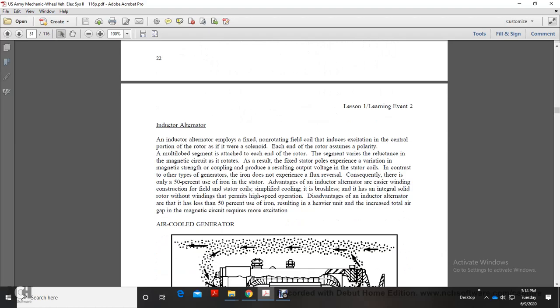All right, your inductor alternator. The inductor alternator employs a fixed, non-rotating field for the excitation of the central portion of the rotor. As if it were a solenoid, each end of the rotor assumes a polarity, with a multi-lobed segment attached to each end of the rotor. The segments vary the reluctance in a magnetic circuit that rotates. The result is that the field poles experience a varying magnetic strength, producing the output voltage in the stator coil. In contrast with the other types of generator, the iron does not experience flux reversal. Consequently, there is only 50% use of the iron in the stator.